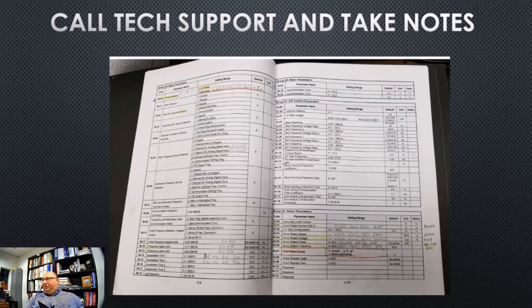This is the key. You're going to get more information, on-the-job training, OJT, if you have the number of the hotline, if you could schedule your VFD changes for normal working hours. The worst thing that could happen is you go there on a Saturday or after hours when the building is closed and you go to do a drive, and you open up the book and you're like, whoa, I don't know what the terminology means between this manufacturer versus this manufacturer. I don't know where to start.